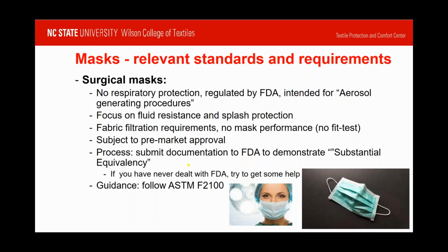So then we move to the surgical masks. As I mentioned, no formal respiratory protection. The primary intention is different, although there are requirements for filtration of particles and aerosols. But the focus is on fluid resistance and splash protection primarily. As mentioned, it's subject to the pre-market approval, which means you need to collect the data and the proof of testing and testing certificate by third-party testing and submit your documentation to the FDA to show that substantial equivalency.